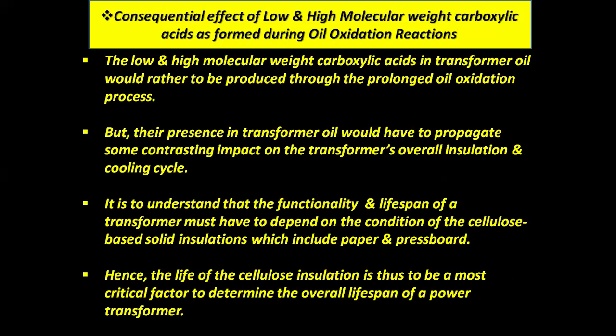Consequential effect of low and high molecular weight carboxylic acids as formed during oil oxidation reactions. The low and high molecular weight carboxylic acids in transformer oil are produced through the prolonged oil oxidation process, but their presence in transformer oil has some contrasting impact on the transformer's overall insulation and cooling cycle.